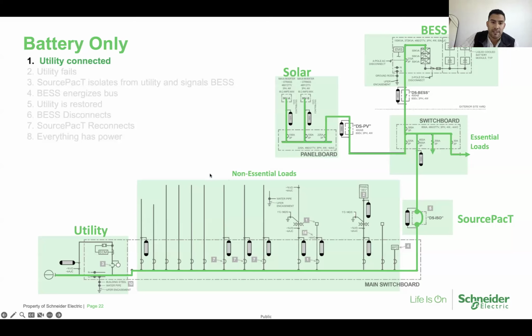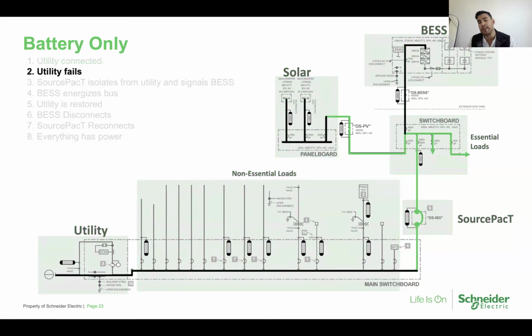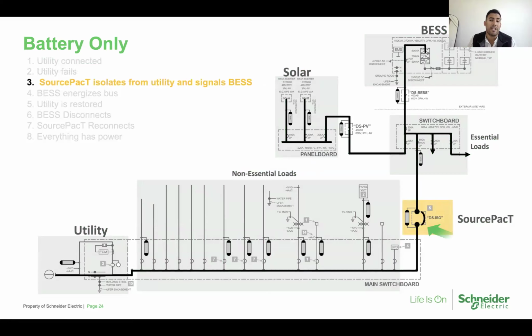The beauty behind this device, as I mentioned, is in the event of utility outage, your entire system here goes dark. The inverters and the photovoltaic and energy storage system are designed to shut down when you lose that anchor resource. So with that in mind, SourcePacT detects that power has been lost, and those inverters essentially wait for a very basic level controller. Some people reference it as a microgrid controller, to send a signal to the inverter systems to come back online, or not become the emergency anchor resource to provide backup power. And that's what battery energy storage systems have the feature to do.